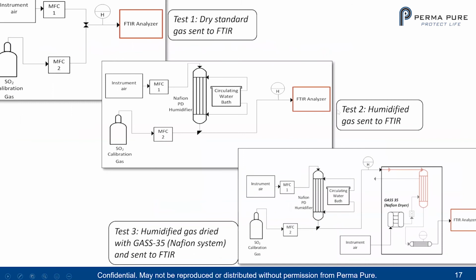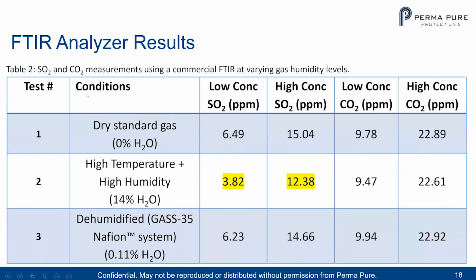So let's look at these setups. Here, test 1, what we were doing is just taking the instrument air and mixing it with the calibration gas to send to the FTIR analyzer. The second one is using a humidified instrument air and mixing it with the calibration gas to the FTIR analyzer. And then the third test was similar to what we showed you on how we did the tests on the Nafion system, except this time we used the Gas 35, not that Gas 6080. So we took that humidified gas and we brought that into the GASS-35 system. And then after it was dried, so we humidified it, then we dried it, then we brought it to the FTIR analyzer. And these were our results, which are very interesting.